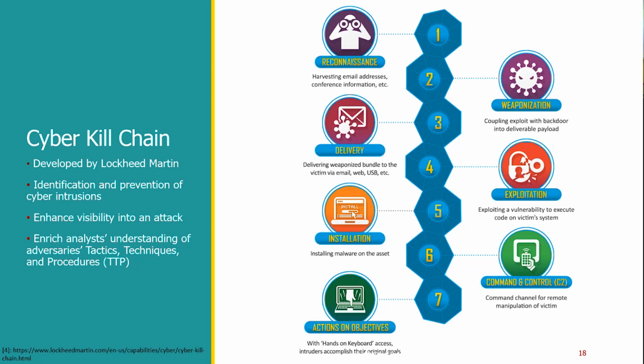Once the malware is in the network, you have the phase in which it is able to locate the attacker infrastructure, and so it's able to use a tunnel to perform malware updates, change its behavior, or start the physical attack. That happens during the command and control phase. In the last phase, we have the actual cyber attack happening. We have the actual opening of circuit breakers, the deletion of data, or the encryption if it is a ransomware attack.